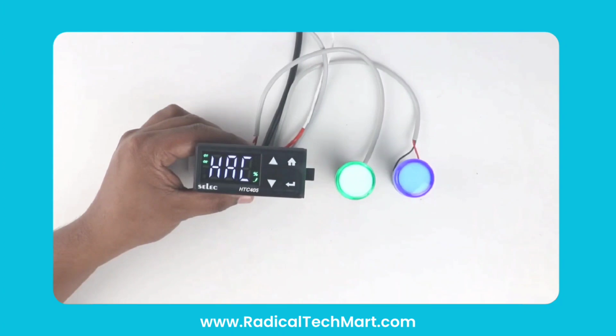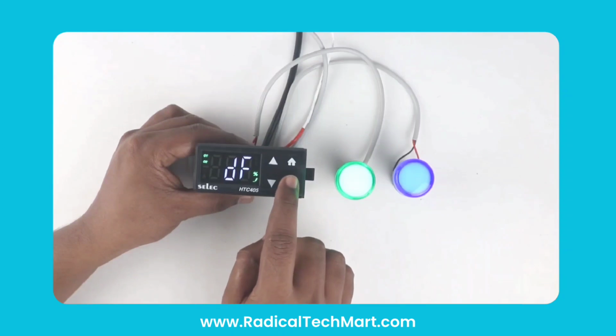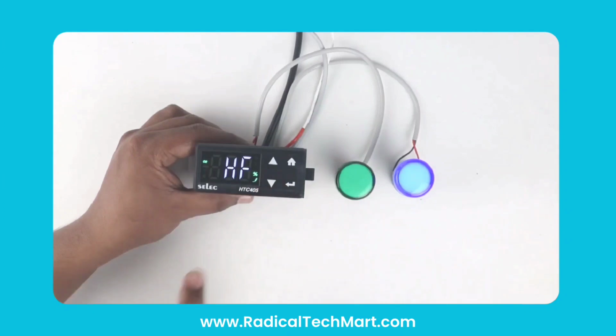Now, the humidity control mode appears. The default is DEF, which means dehumidifier mode. In this mode, if the humidity goes above the set point, the relay will turn on. Alternatively, you can select humidifier mode, where the relay turns on only if the humidity is below the set point, and turns off when it goes above. I will set it to dehumidifier mode and press Enter to save.